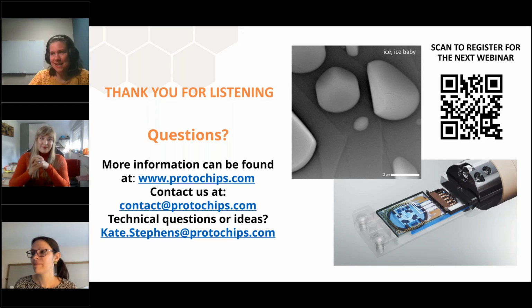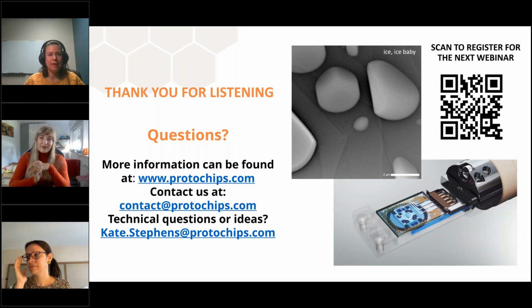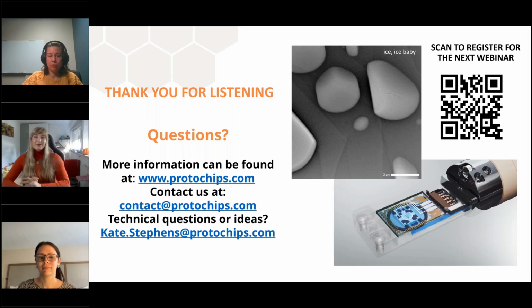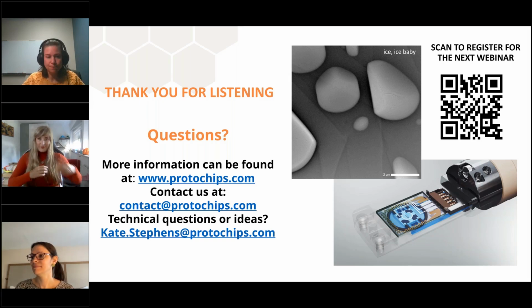Yeah, so that's actually one of the reasons that's on my slide: I wonder the same thing. The way I would design the experiment, if I were the one doing it, is that I would have my reference electrode set up. I would figure out what my reference potential is, and then I would cool at the tip and see how much it shifts. And then I would cool the external reference electrode as well, and see if that brings it back or if there's any shift at all, because there very well might not be.